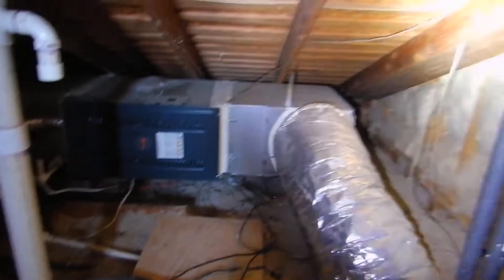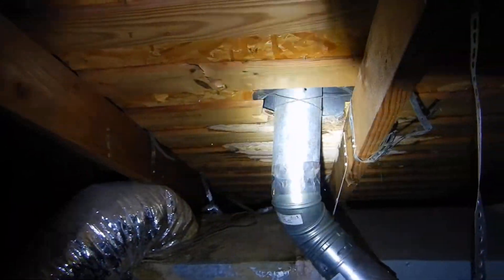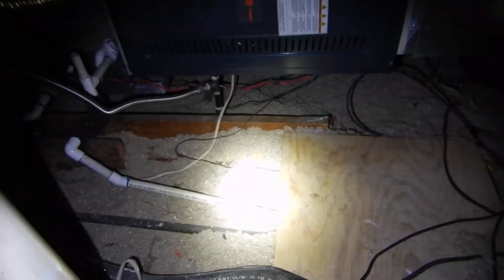But that's not why we're up here — we're up here to talk about the attic. Look at the ceiling; this light doesn't work. The roof also looks a bit cruddy over there. The real point of this video is that we do not have sufficient service access in front of the east indoor air handler.